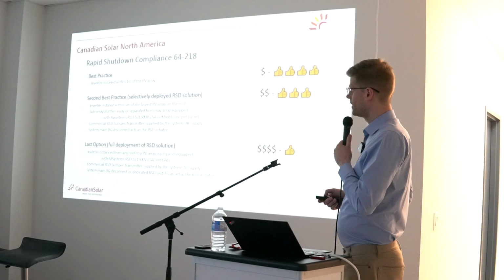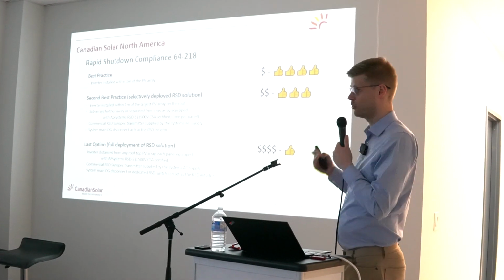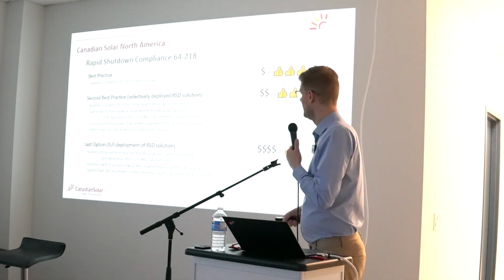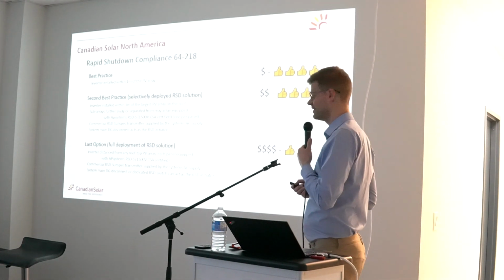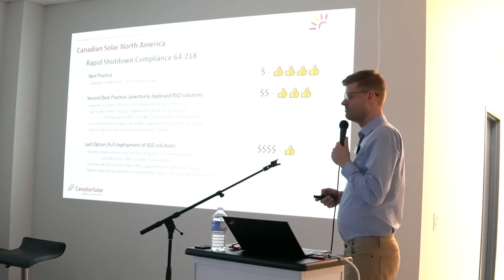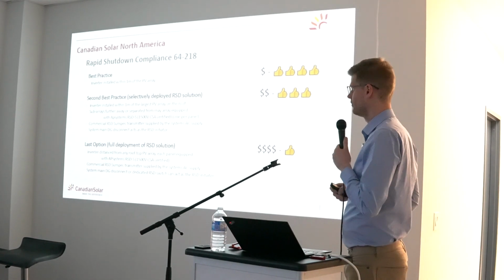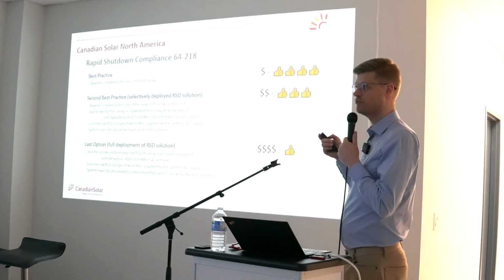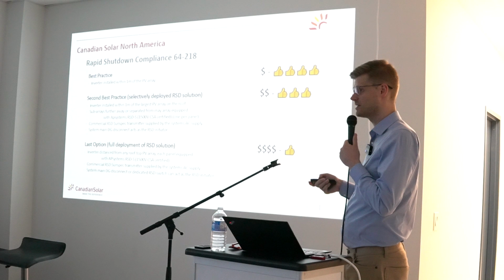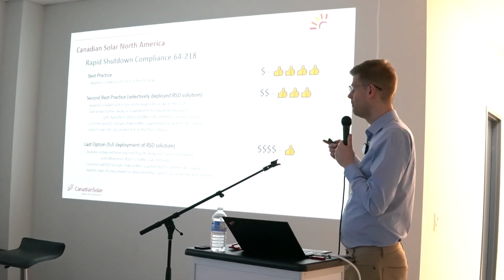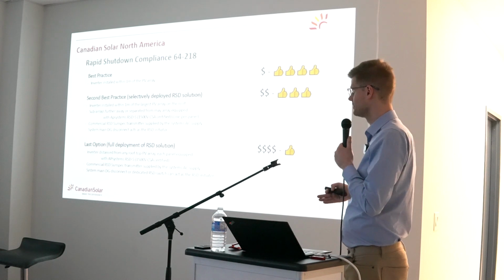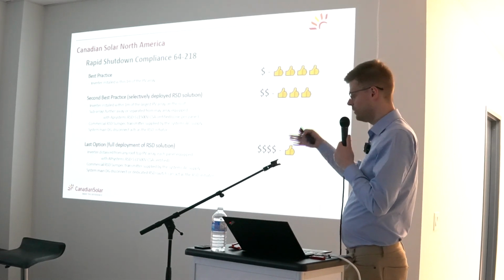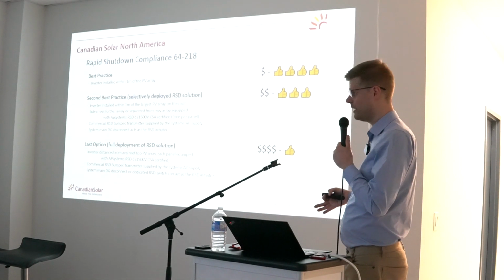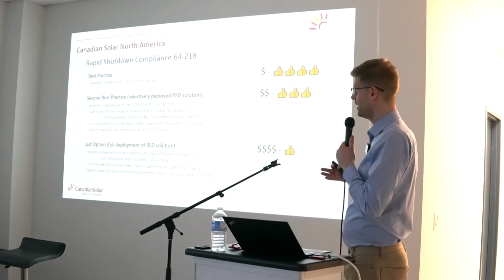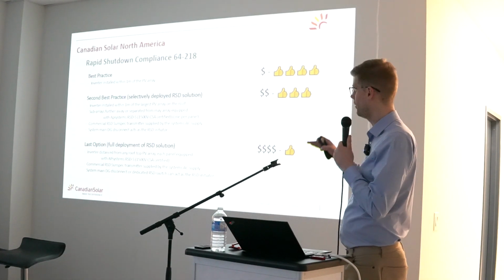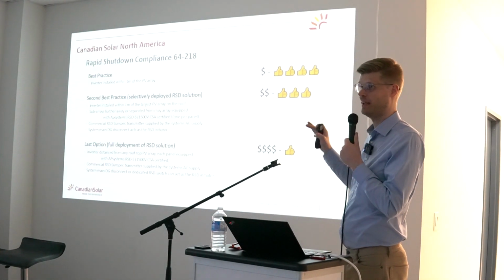At the end, we quickly want to look into rapid shutdown and the best practices for commercial large-scale systems. And I have here a few thumbs up and not so many thumbs up. So I would say probably 98% of large commercial rooftop systems try not to use rapid shutdown devices and design the system instead to be rapid shutdown compliant by placing the inverter within 1 meter of the array. The code allows you to place the inverter adjacent to the array. You are still within the 1 meter. You have no uncontrolled conductors this way on the DC side, and you're automatically code compliant without any money spent on dedicated rapid shutdown systems.